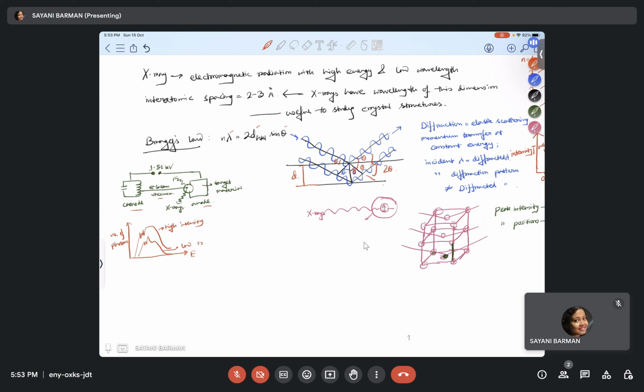So, if the potential difference between the anode and cathode is increased, electrons gain more energy prior to the collision with the target. Both the height of the peaks and the highest possible energy of the X-rays increase. The target anode is angled to ensure that the X-rays are directed through a window in the desired direction. Everything inside the X-ray tube is manufactured in such a controlled way that only a small portion of X-rays is directed out through a certain size of window and is detected by the detector after diffraction and reflection.